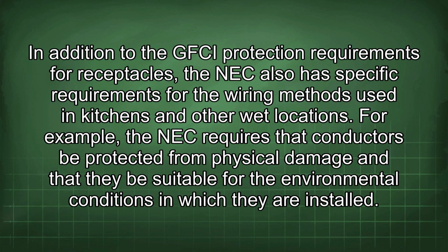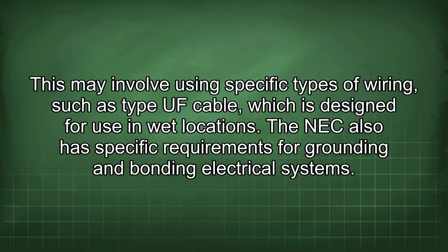In addition to the GFCI protection requirements for receptacles, the NEC also has specific requirements for the wiring methods used in kitchens and other wet locations. For example, the NEC requires that conductors be protected from physical damage and that they be suitable for the environmental conditions in which they are installed. This may involve using specific types of wiring, such as type UF cable, which is designed for use in wet locations. The NEC also has specific requirements for grounding and bonding electrical systems.